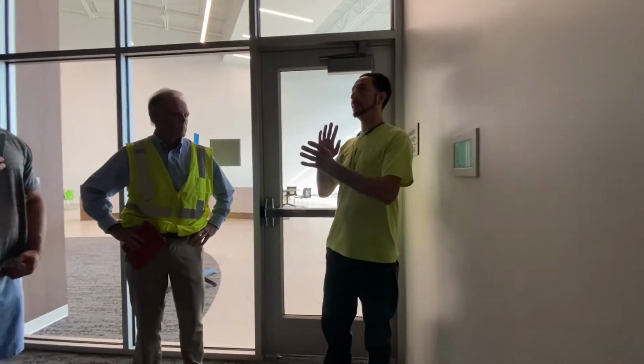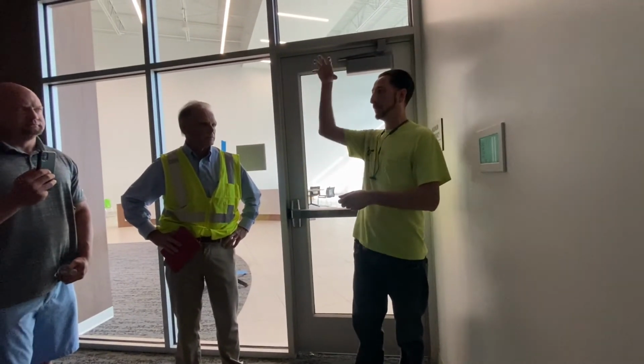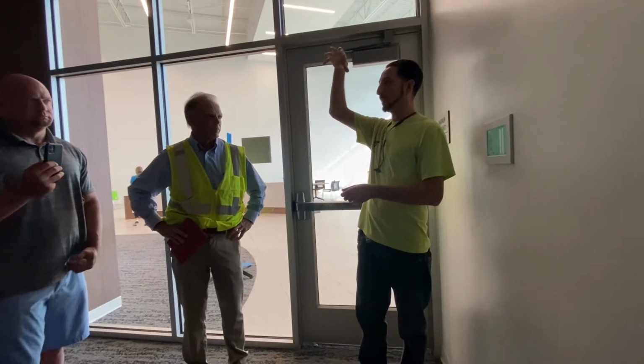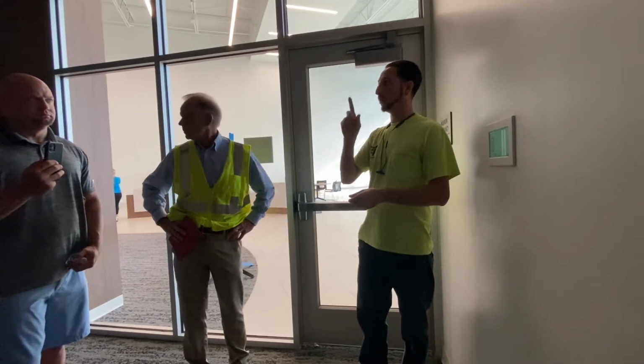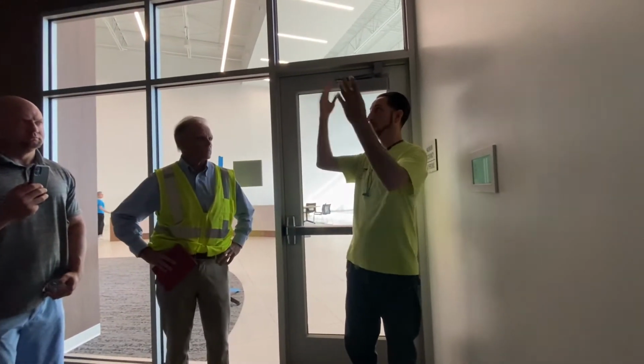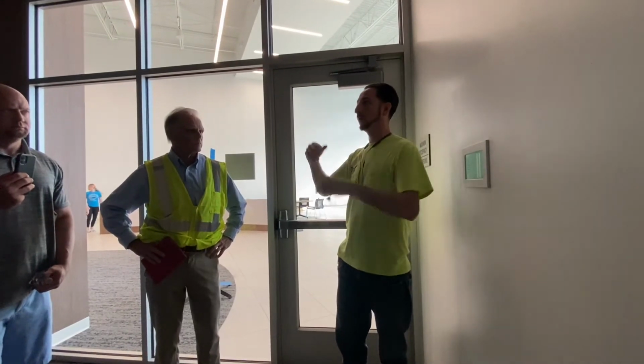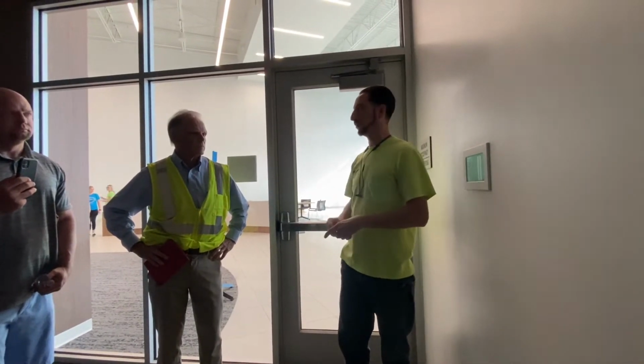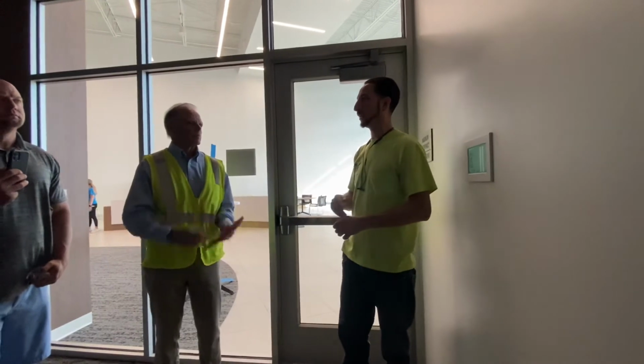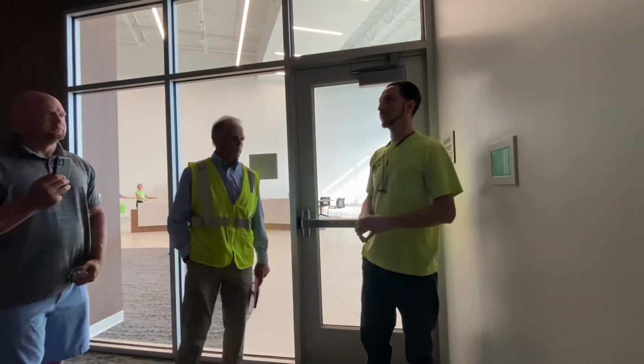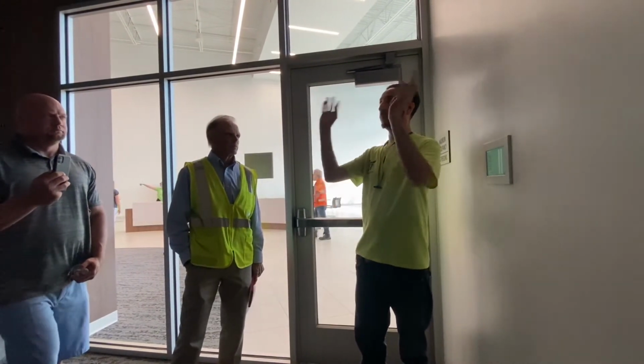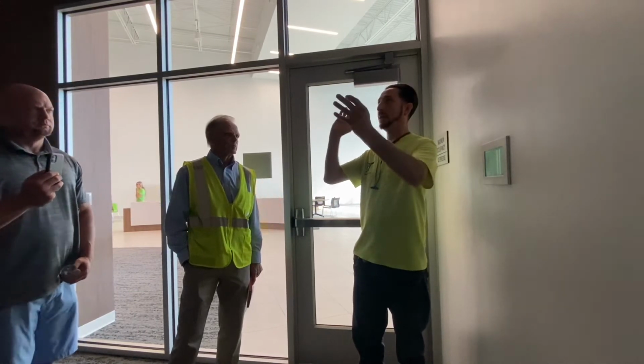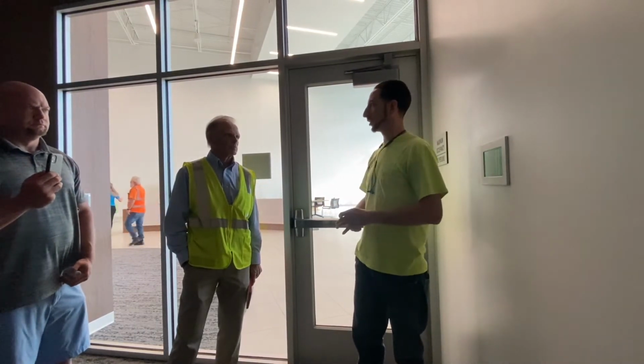You can take the delay off the relay, but the relay has to be exposed for the inspector to see it. It has to be visible. So these relays are within the ceiling and they're concealed, so it has to have the relay on it. You'll see that throughout the building. When you go into certain rooms, you'll click the lighting off. You'll have the regular lighting go off immediately, and then about 2 seconds later, the emergencies will shut off behind that.